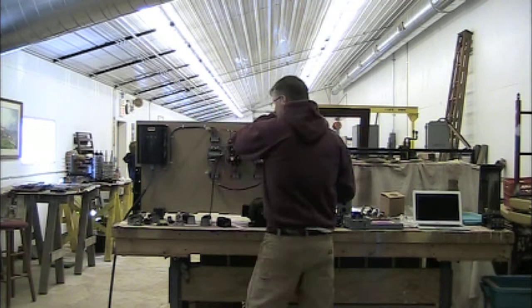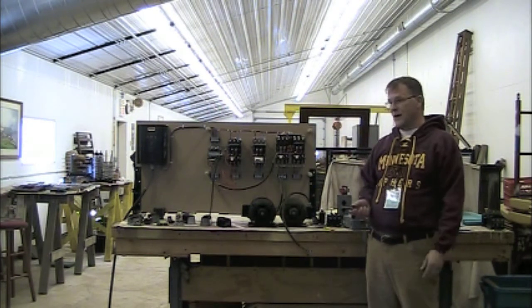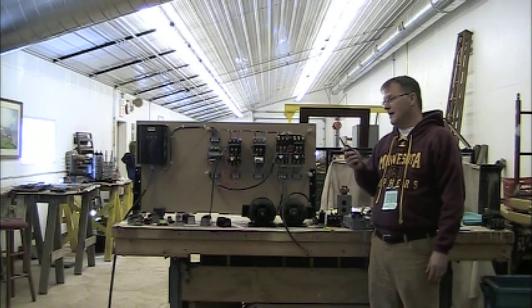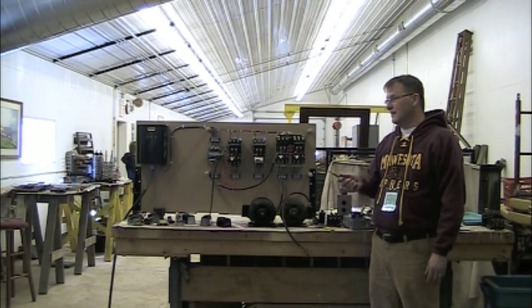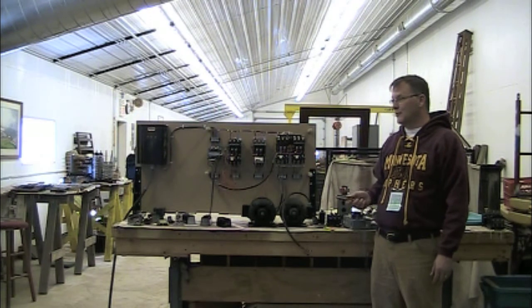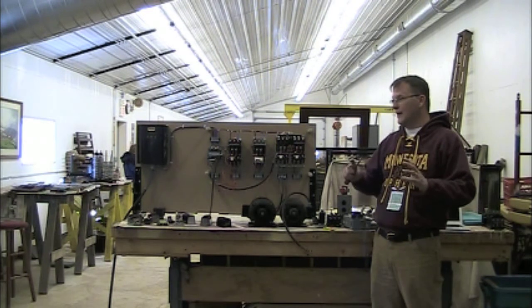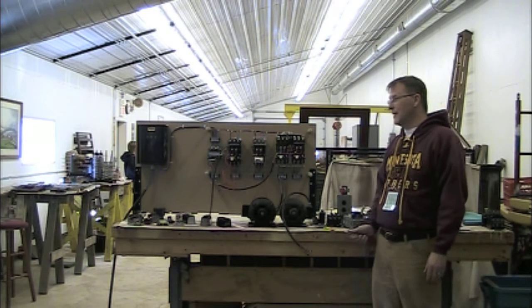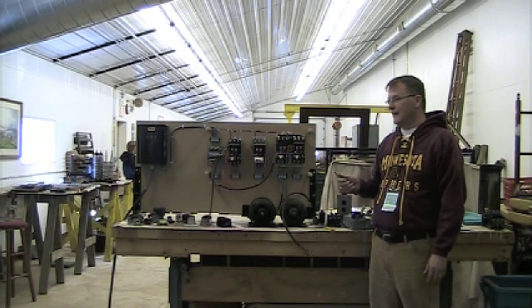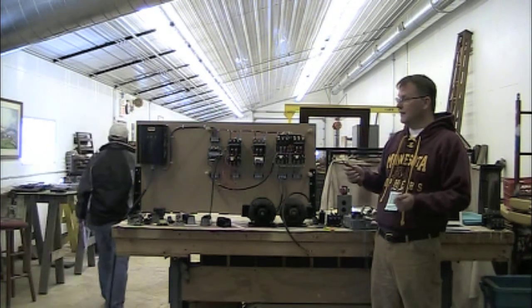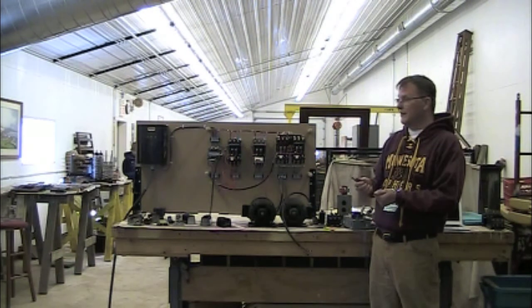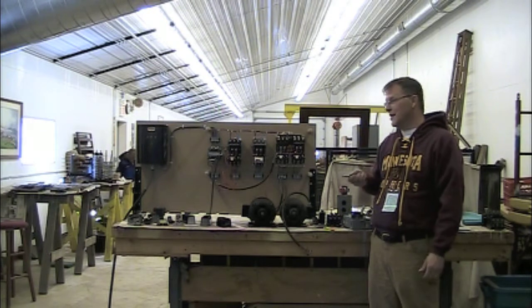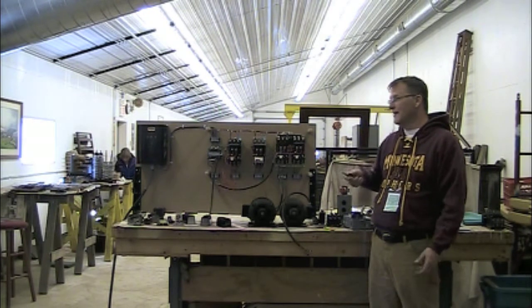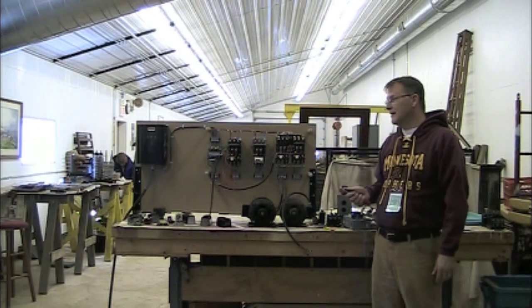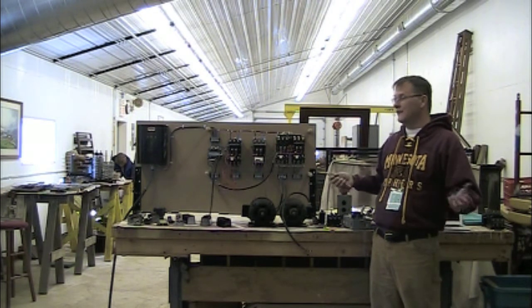Well, what's really complicated are the Oliver 51 three-phase headstocks, which have dual sets of windings. They're constant horsepower, consequent pole, 4-speed motors. So you've got 2 distinct sets of windings. There's 14 leads coming out of the motor, and the switching of the contactors has to break the winding set you're not using, because otherwise you're generating voltage back coupled from the rotor, and you'll actually interfere with each other if you don't open that other set of windings. So that's even more complicated.